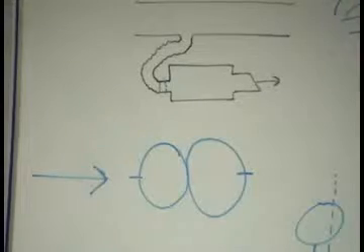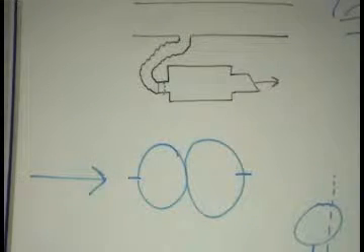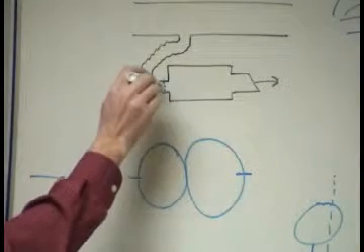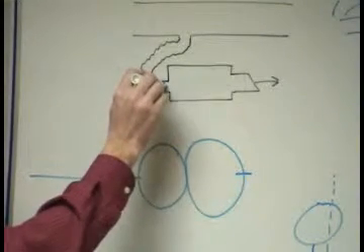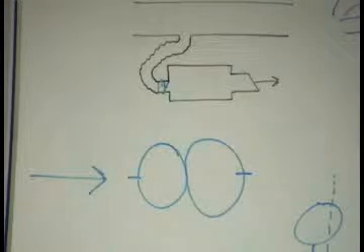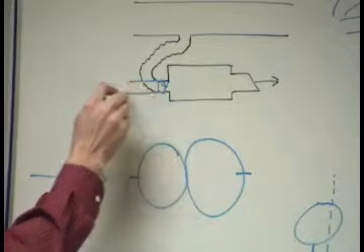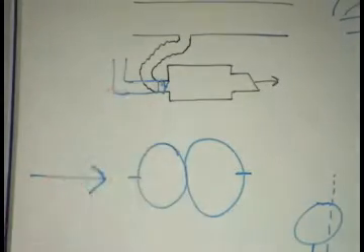So we've all seen this installation, right? Fronts come down, they've got flex, usually about 13 foot of it. It's pinched off right there at the opening because the light was right there, so they had to cram it in there to make it work. And you've got no straight duct. Here's our pitot tube right here. Here's our damper right behind it. There's nothing straight about any air anywhere near there. So if we can get a little bit of straight air before that box, you've got half a chance of getting a decent reading.